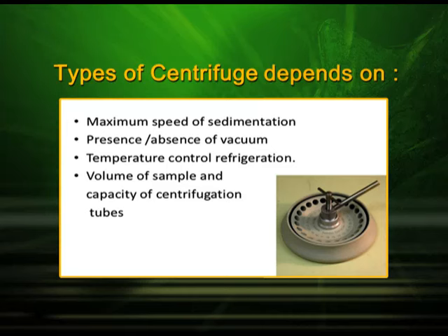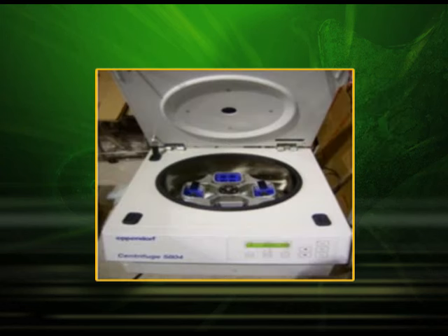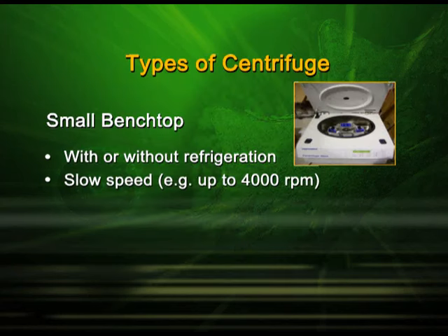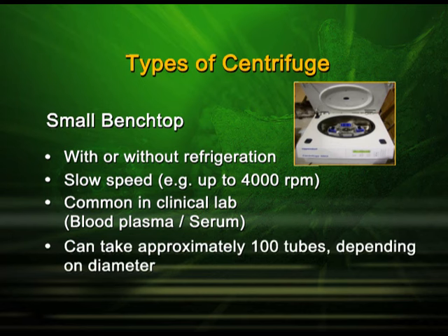For example, you might have a sample of around 1.5 milliliters or around 100 ml — so it depends upon the volume. The first type is the small bench top or low speed centrifuge. It looks something like a grinder, it can be with or without a refrigerator, runs at a very slow speed up to 4000 RPM, and is mostly used in clinics for separating blood plasma or serum. It can take approximately 100 tubes depending on diameter.